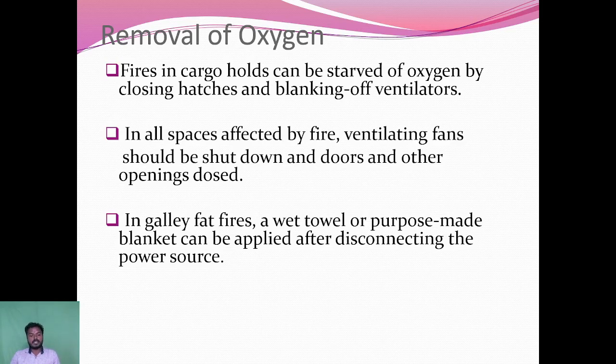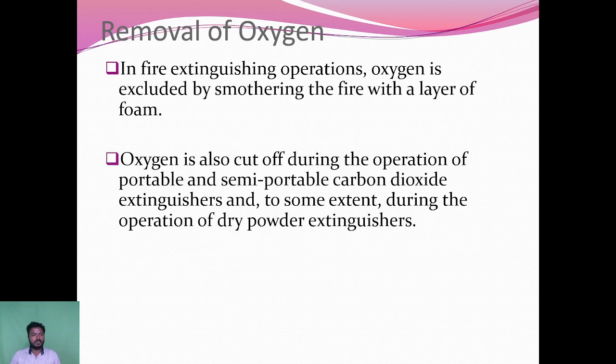In all spaces affected by fire, the ventilation fan should be shut off, and the doors and other openings must be closed. In galley fat fires, a wet towel or purpose-made blankets can be applied, after disconnecting the power source. If the fire catches in the cooking area, we wet the towel and put out the fire. Or there are some special types of blankets. We spread them over the fire area, and the fire will be cut off.